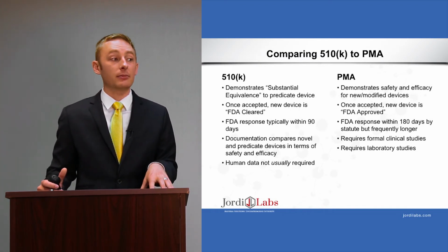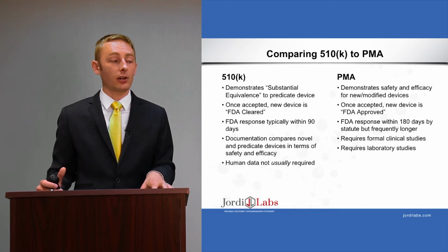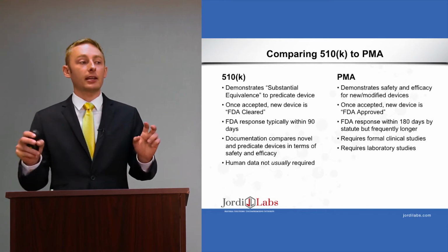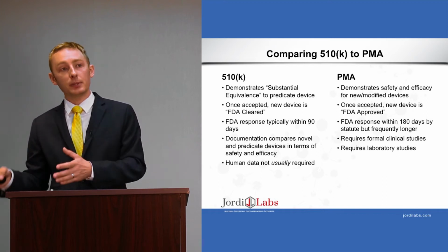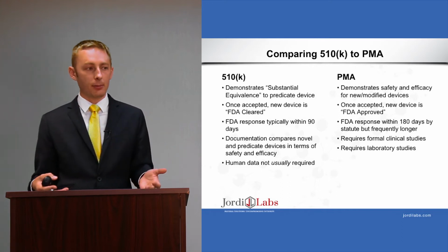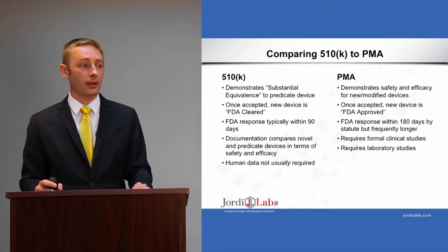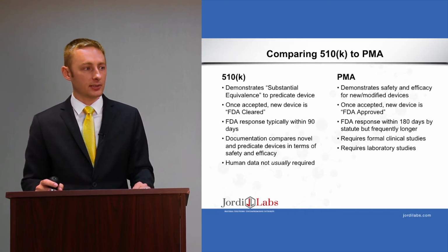So the 510K demonstrates substantial equivalence to a predicate device. Once it's gone through the process, the new device is FDA cleared. And this is in contrast to the PMA process, which once it's gone through the PMA process, that device is then FDA approved. And so it's a very big distinction to make for these two processes.